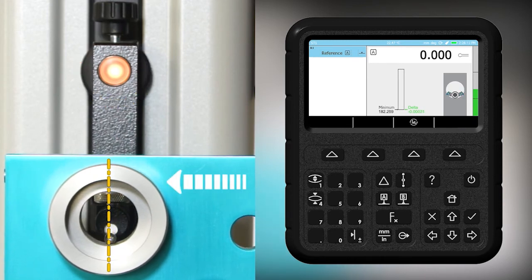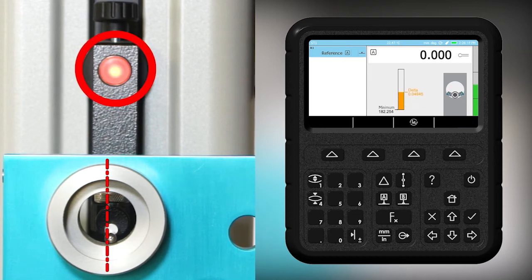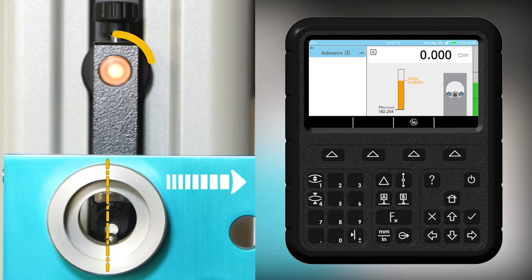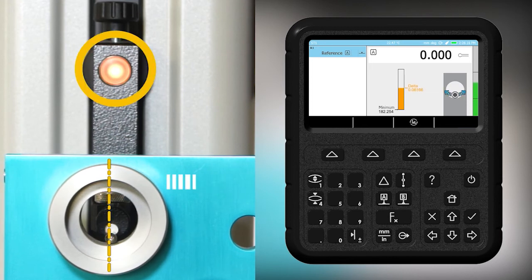As soon as the point has been passed, the LED color turns red, which means that the probe is now beyond the culmination point. Sweep the probe back in the bore until it reaches the minimum point again.